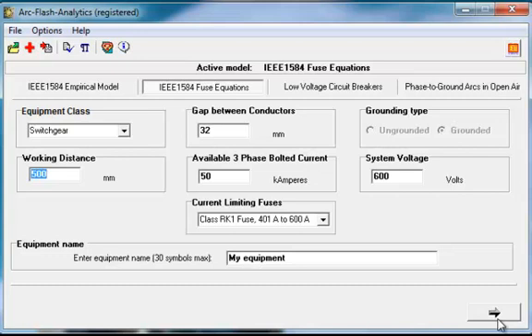For cases where voltage is different than 600 volts, or available fault current and gap is outside the range of the model, the IEEE 1584 Empirically Derived Model can be applied and it is included in the ArcFlash Analytic Version 4.1 calculator.